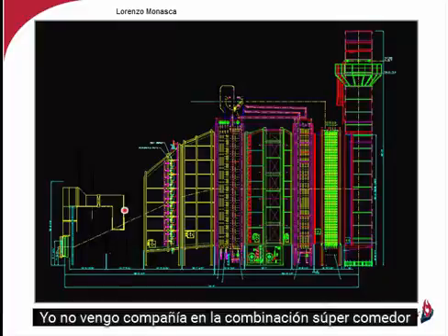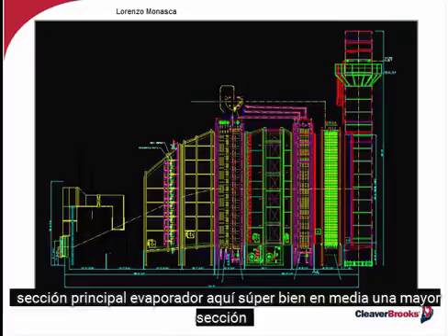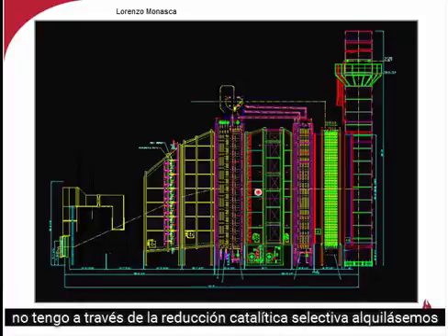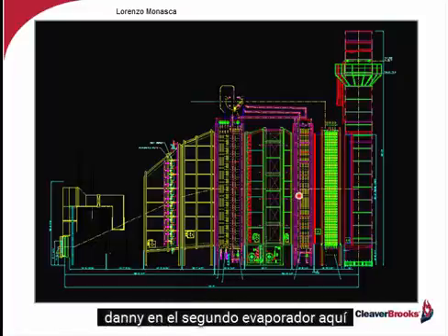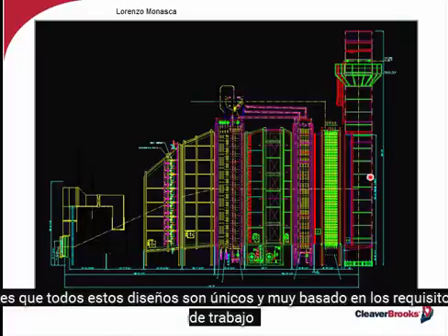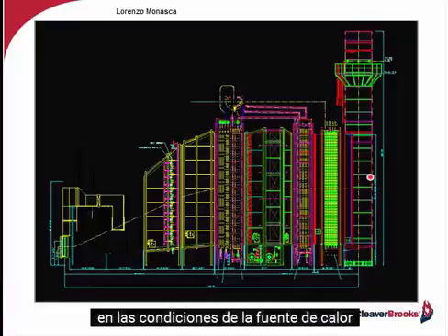I then come into the combination superheater and main evaporator section right here. Superheater and main evaporator section. I then pass through the AIG and selective catalytic reduction portion, then into the second evaporator right here, then into the economizer, and then out the stack. So again, what I'm trying to show here is that all of these designs are unique and vary based on the job requirements and the heat source conditions.